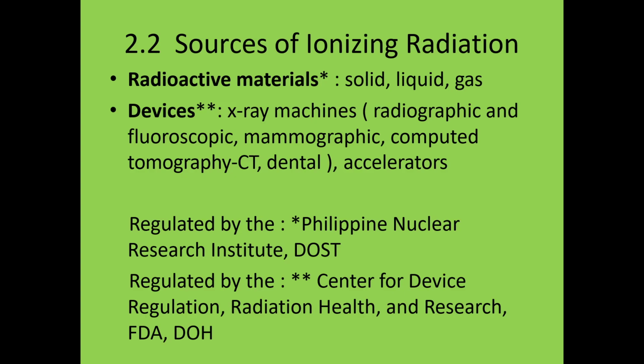So devices. Okay. So ito yung mga machines na ginagamit natin sa medical field, but also there are accelerators. Okay. So these accelerators are regulated by the PNRI. Okay. So yung accelerator and radioactive materials are regulated by the PNRI, which is under the Department of Science and Technology, while the other devices such as X-ray machines, radiographic and fluoroscopic, and also CT, including the dental X-rays, are under the Center for Device Regulation, Radiation Health, and Research of the Department of Health. Sila yung nagbibigay ng license.